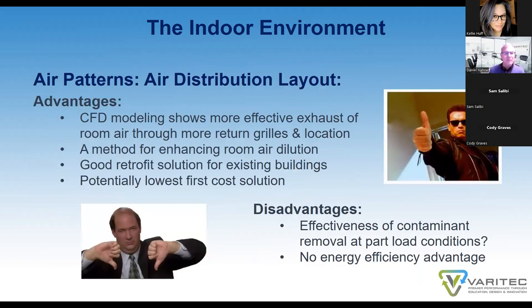So what are the advantages of looking at the air distribution layout? Well, CFD modeling shows more effective exhaust of room air through more return grills and locations, a method for enhancing room air dilution by properly placing diffusers within a space. It's a good retrofit solution for reducing the risk of infection in existing buildings and potentially the lowest first cost solution. The disadvantages of air distribution layout are the effectiveness of contaminant removal and validation thereof, especially at part load conditions. And it does not offer an energy efficiency advantage.